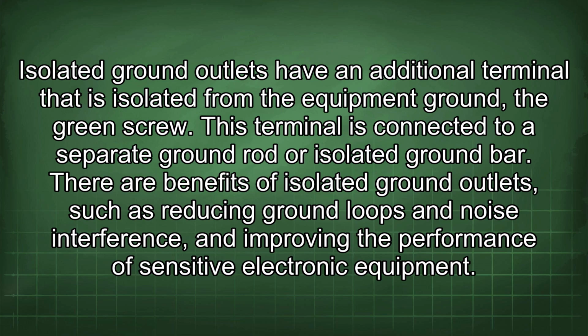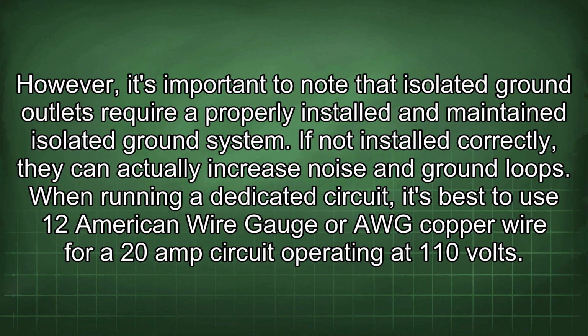There are benefits of isolated ground outlets, such as reducing ground loops and noise interference, and improving the performance of sensitive electronic equipment. However, it's important to note that isolated ground outlets require a properly installed and maintained isolated ground system. If not installed correctly, they can actually increase noise and ground loops.